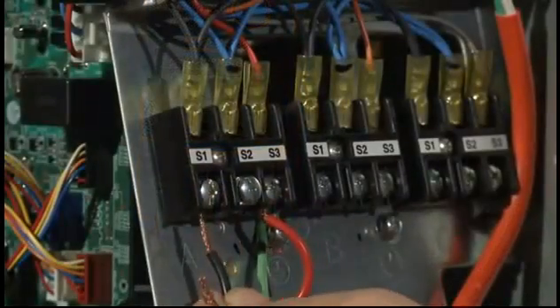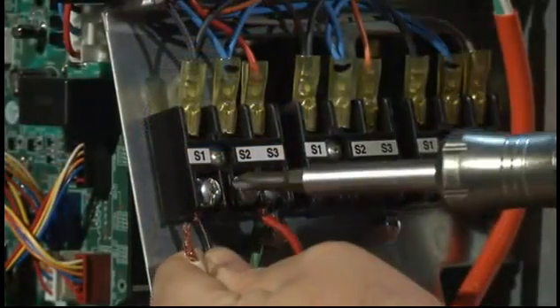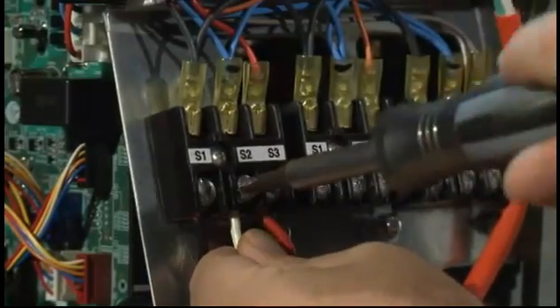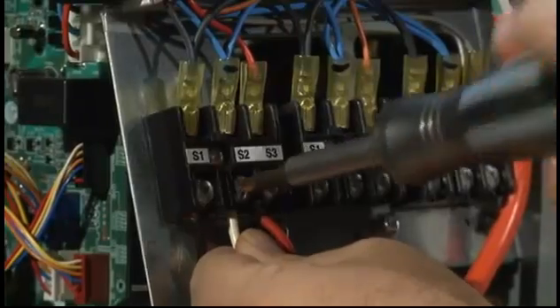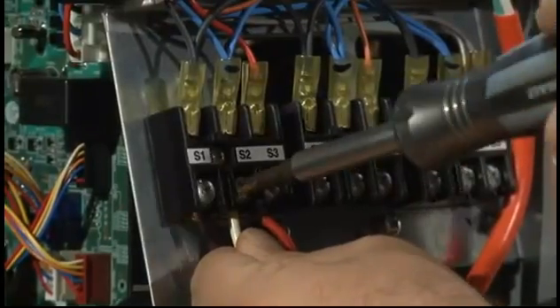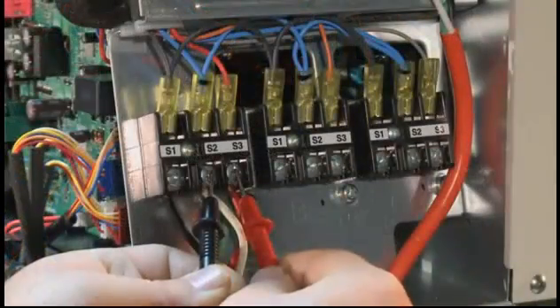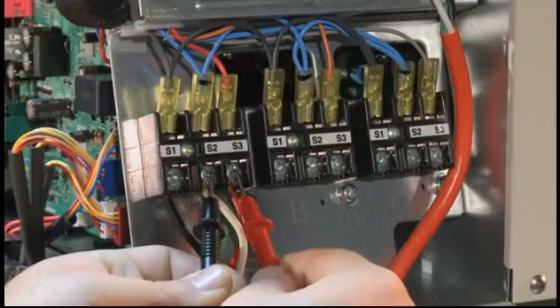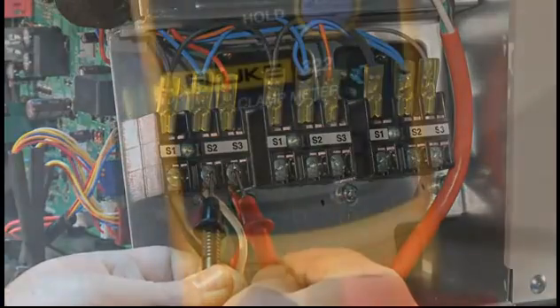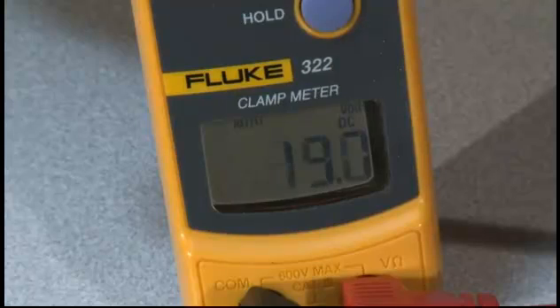The easiest way to verify this would be power down your outdoor unit and swap S1 and S2. Keep the power off for at least 3 minutes to reset any error codes. And once you turn the power back on, recheck your S2 and S3 DC voltage and verify that you do have a good fluctuating communication voltage between 10 to 24 volts DC.